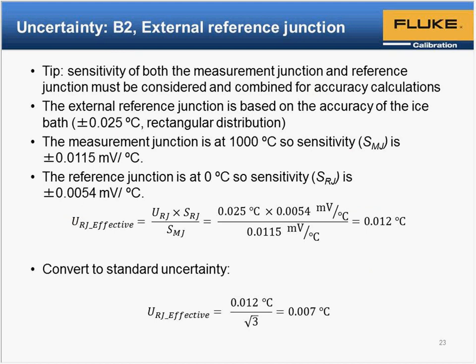Okay, now look at the math involved here. I briefly mentioned earlier, when you're calculating the uncertainty of a reference junction, you need to consider the sensitivity at the temperature of the measurement junction and the sensitivity at the temperature of the reference junction. So let's see what we mean by that.